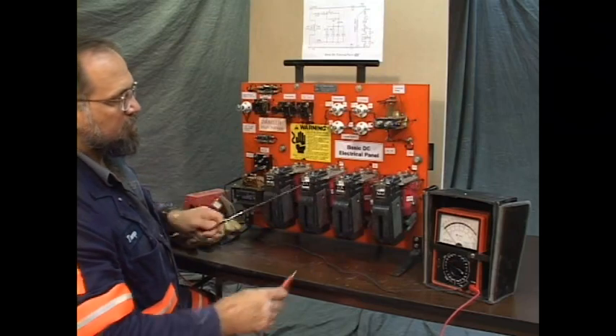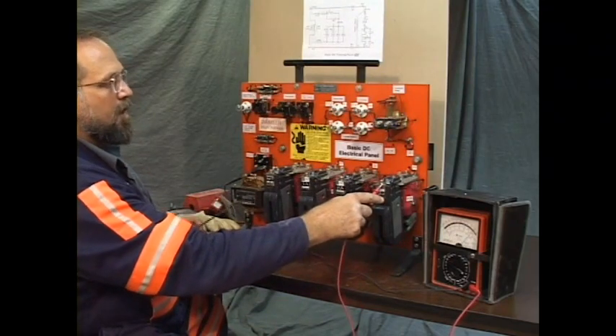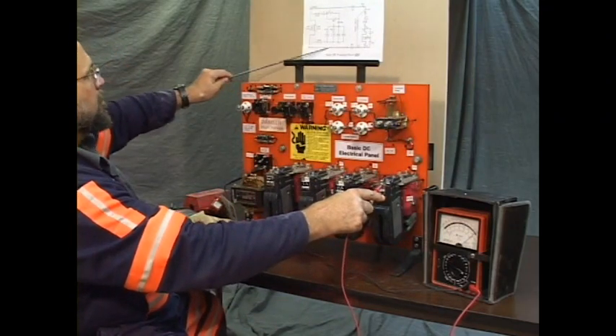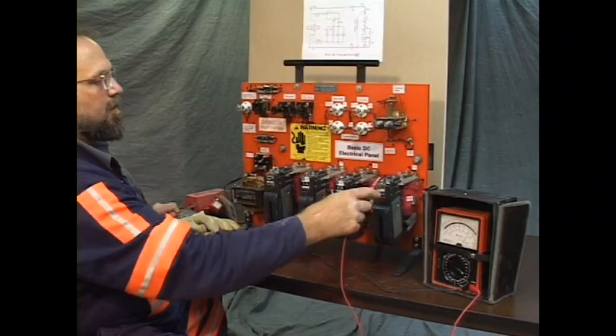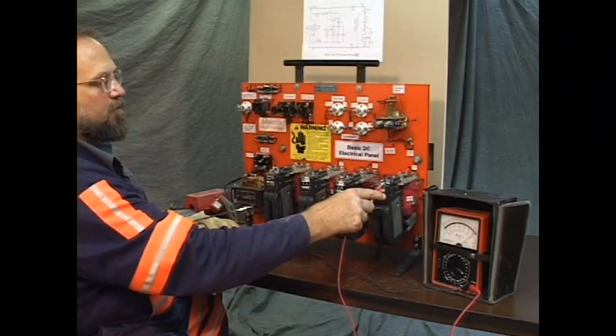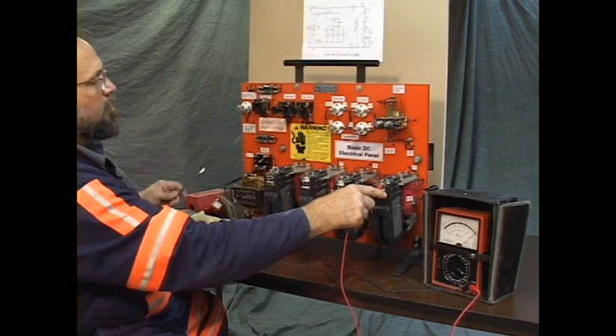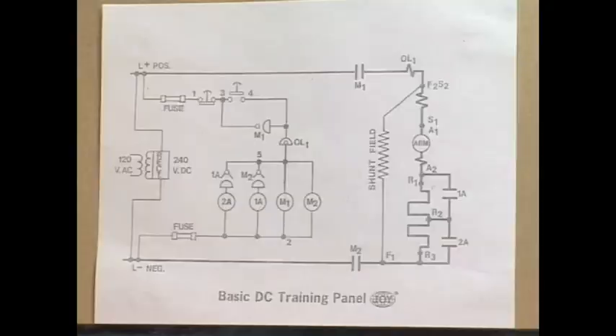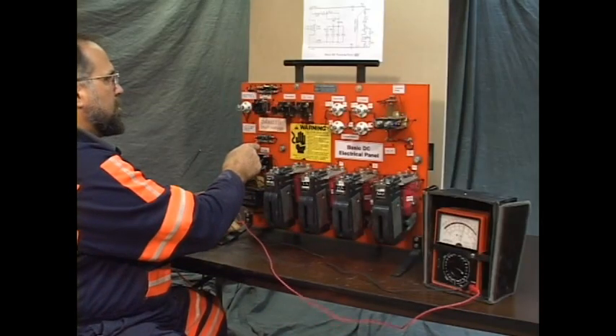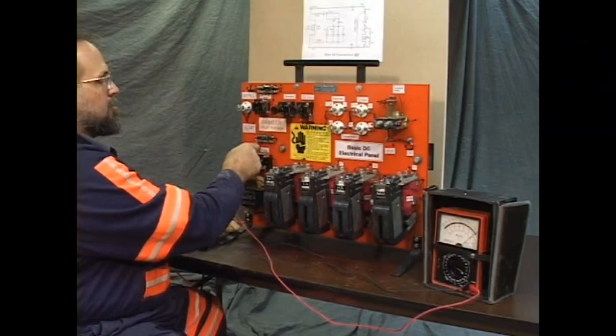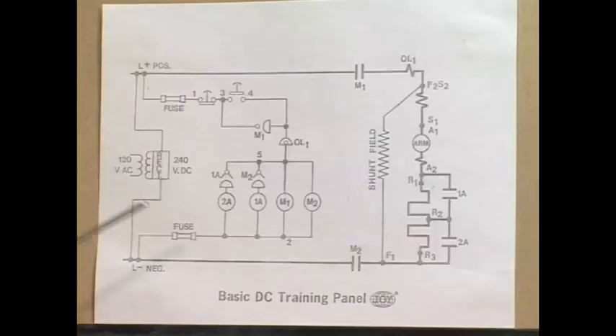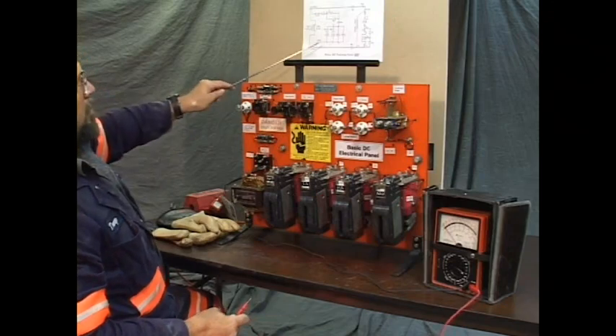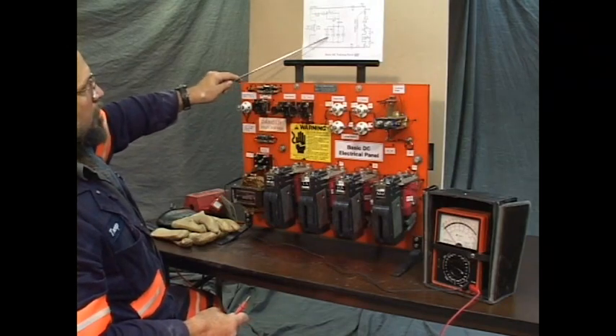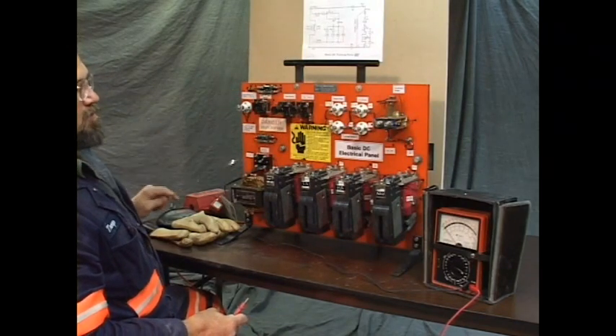First point it goes to, the top front of M2 contactor. That's the negative contactor, the master contactor that controls the negative for the entire motor circuit. The next point, line side of the negative fuse. Here we go. That's good. The load side of the negative fuse, right there, that's good. I like to stay in a line, do it in a proper sequence so that you don't get lost and omit a check.